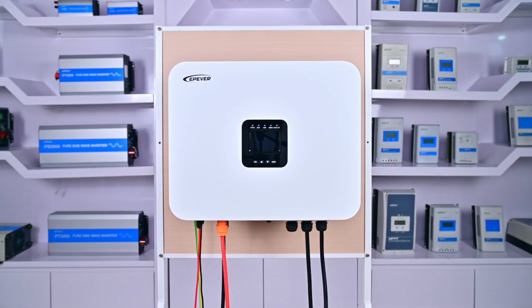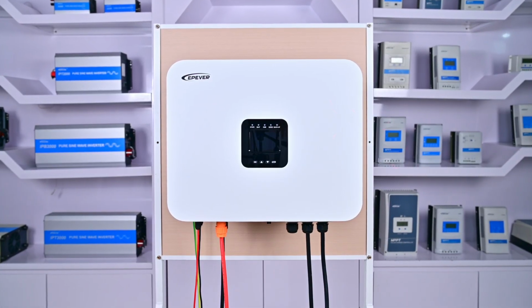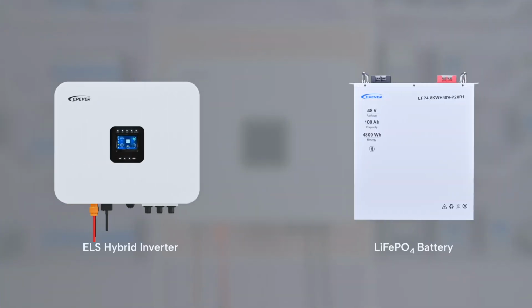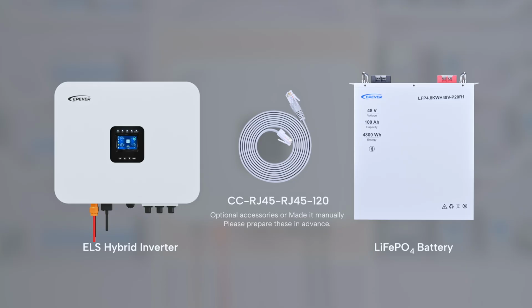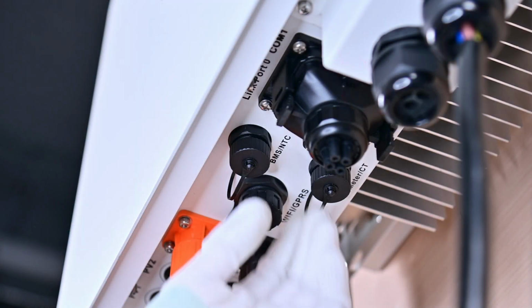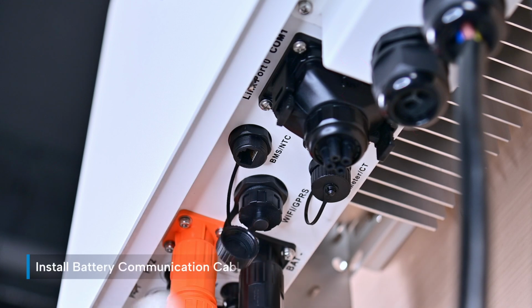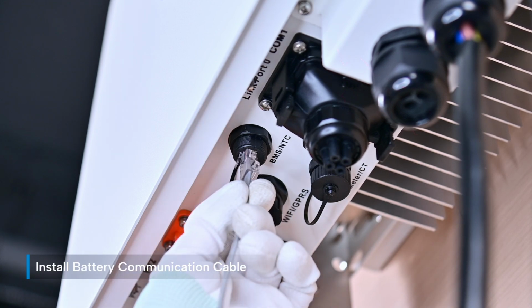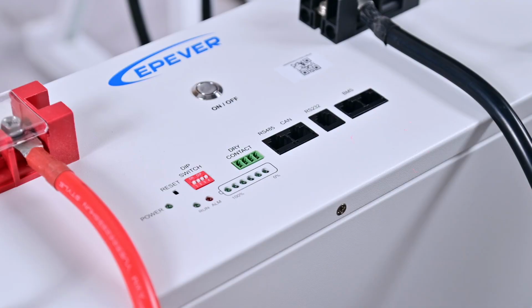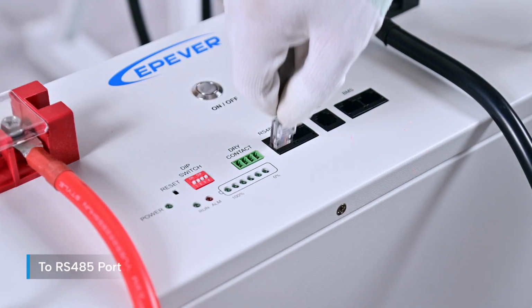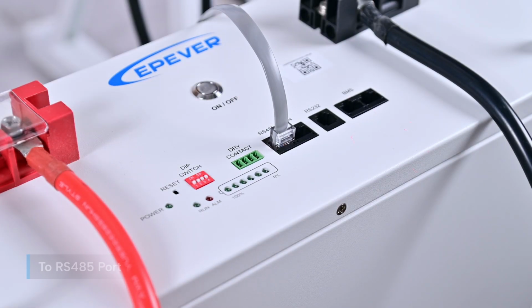Now we connect the necessary lithium battery communication cable and current transformer. The redesigned ELS and lithium battery communication system typically only requires a standard household network cable. If you do not have one, you can make one yourself following the user manual. Please prepare this in advance. Insert one end of the communication cable into the ELS's BMS interface and the other end into the battery's RS485 interface.